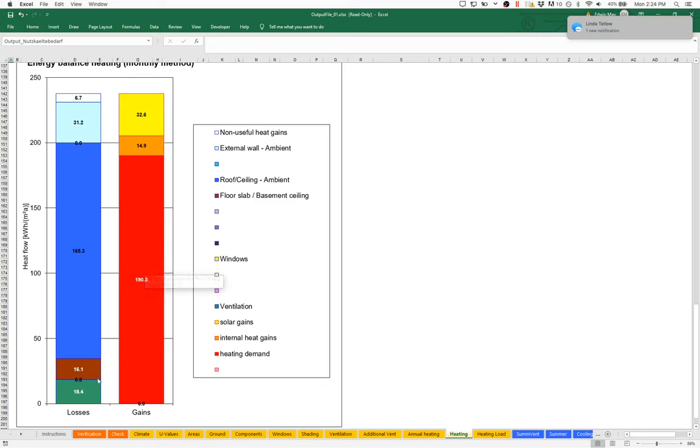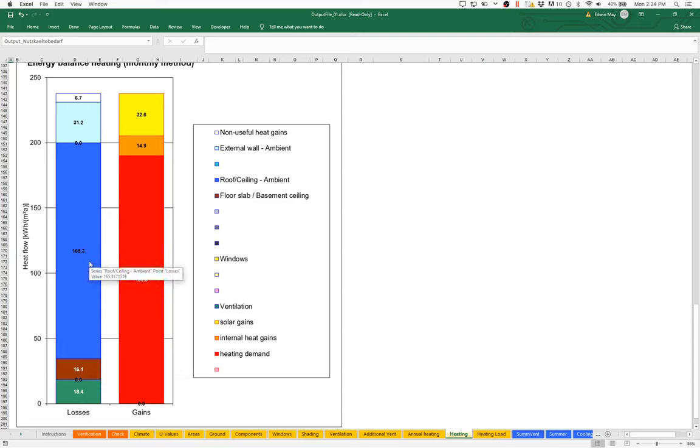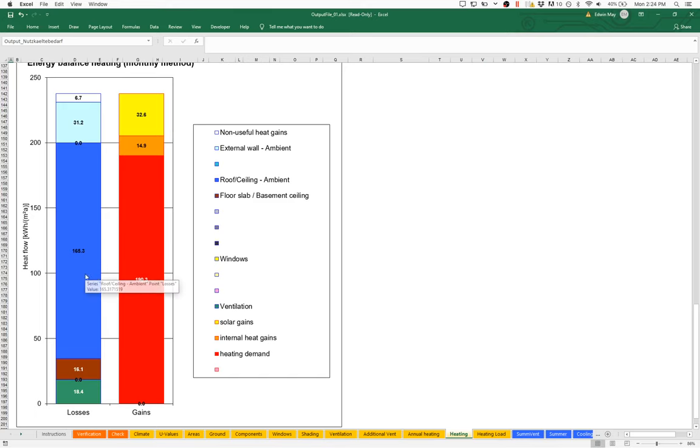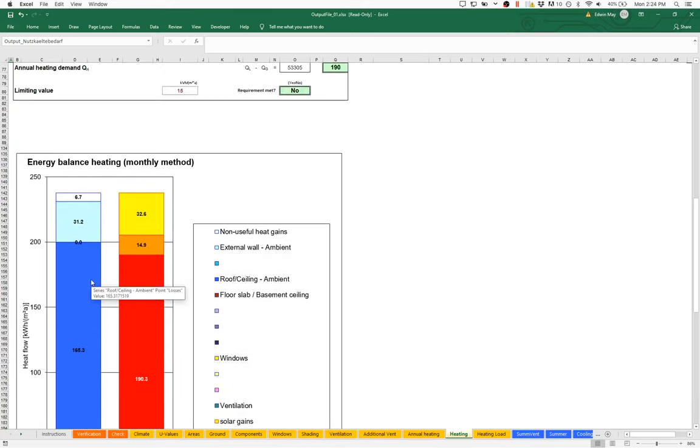What is causing all these losses? If we look at the breakdown, we have some ventilation losses - okay, not crazy, but sure. We have some floor losses, some losses through the floor. And then we have this giant blue bar. What is this? These are losses through the roof. So for some reason, we have really high heat loss through the roof, and then pretty high heat loss through our walls as well. This is an indication that there's something going on with the roof. We have to figure out what's happening with our roof.